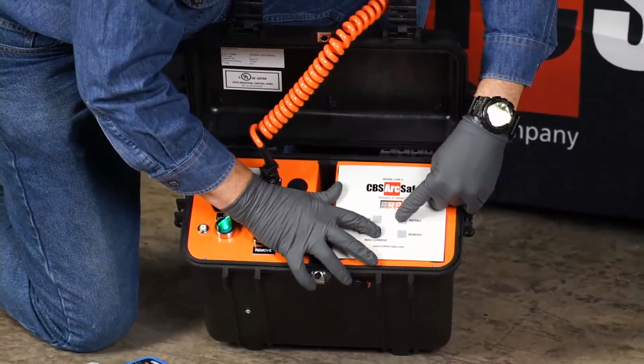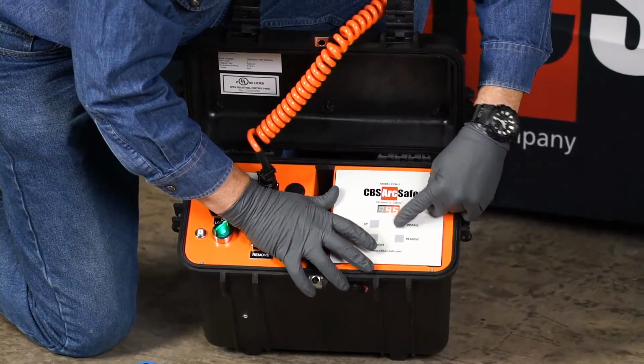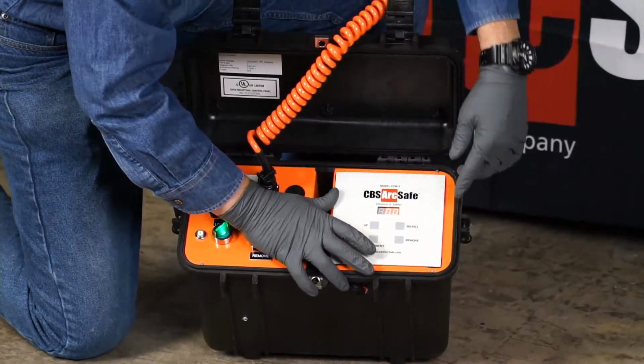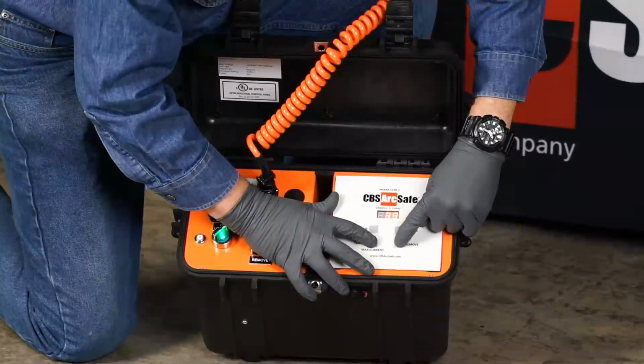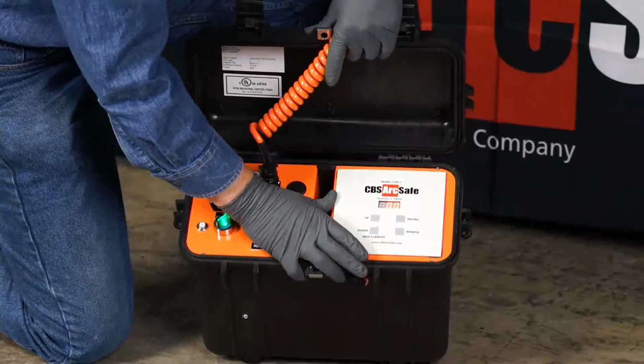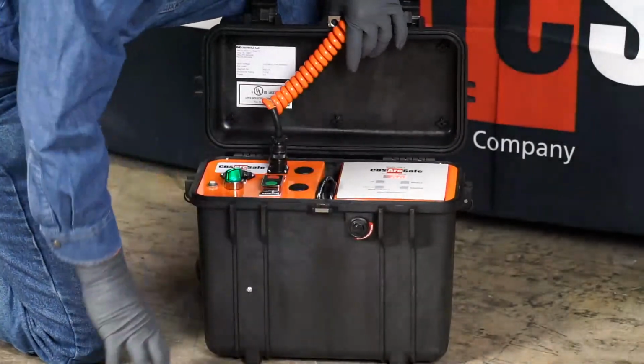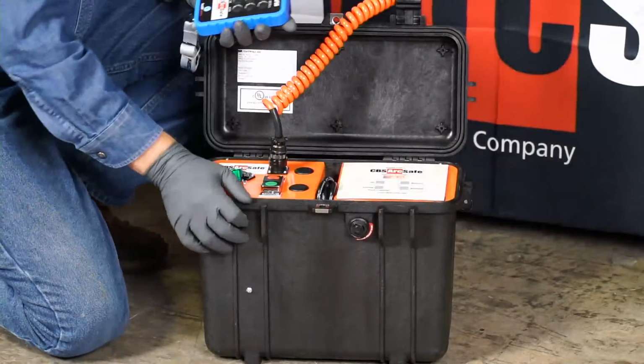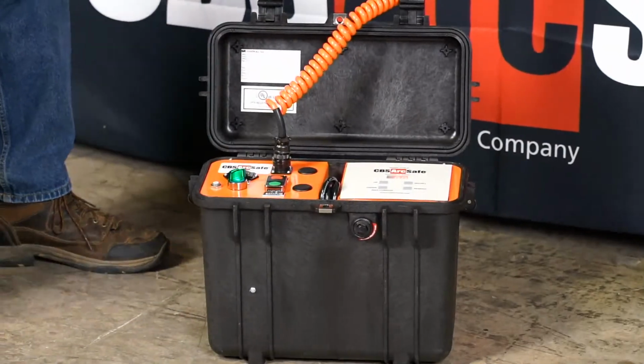Now this breaker is not going to move when we do this. For install, 4.5, and 3.8 for remove. And then we have the clutch set at 18 foot-pounds. So even though the breaker is not going to move, we're going to pretend like it is.